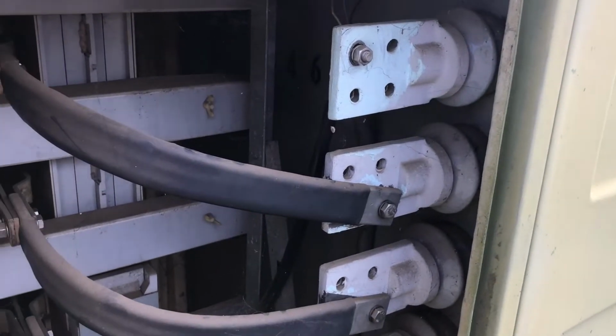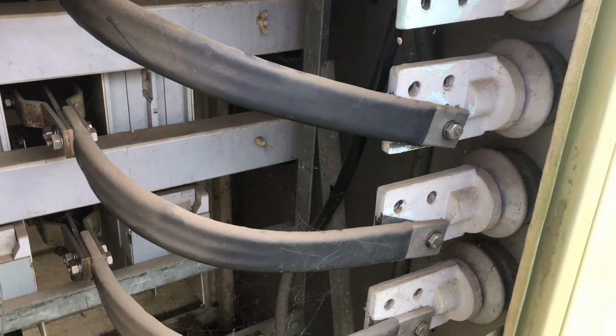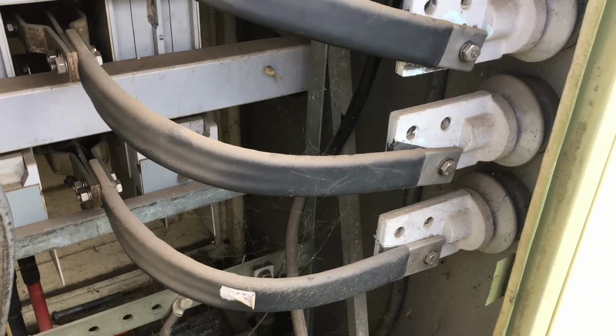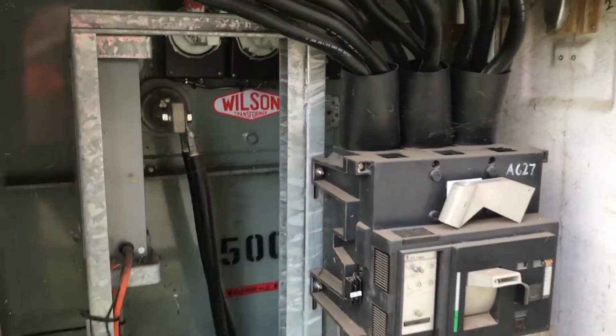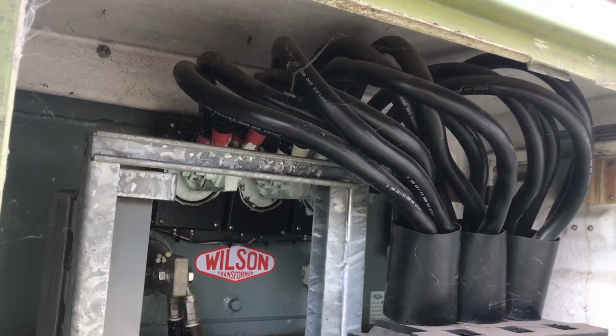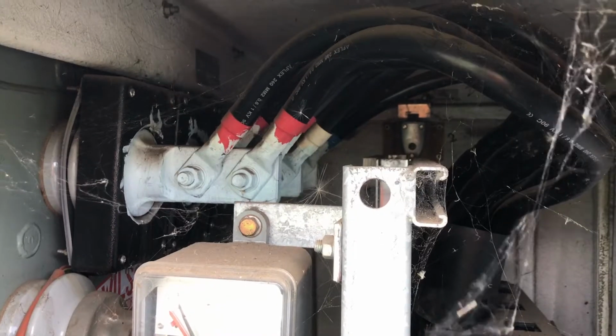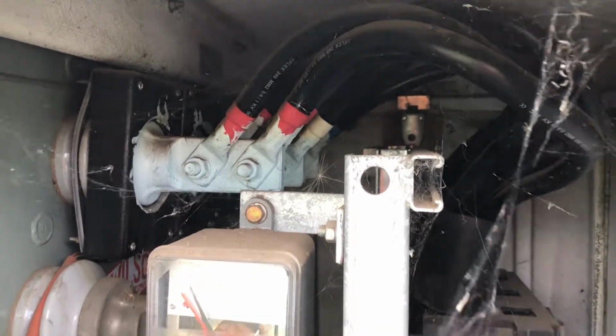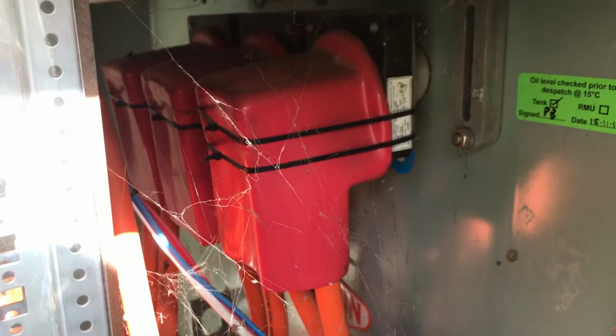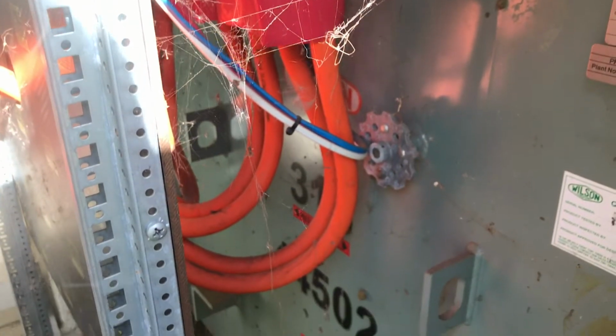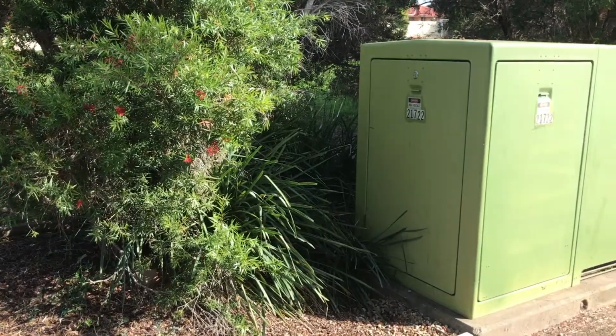Making or breaking ground-mounted transformer connections, either at the transformer bushing or the line side of the main isolator, is not permitted live because the lack of electrical protection means there is extremely high levels of arc flash energy available. For the same reason, working on current transformers on energised ground-mounted transformers which are fitted between the transformer bushings and the line side of the main isolator is not allowed.